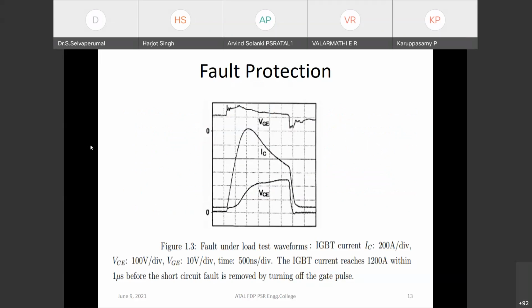So the slide shows fault under load test waveforms. IGBT current is denoted as IC, 200 ampere per division, and collector emitter voltage 100 volt per division. Gate emitter voltage is 10 volt per division. Time is 500 nanosecond per division. Right. So the IGBT current reaches 1200 ampere within 1 microsecond before the short circuit fault is removed by turning off the gate pulse. So here the dynamic performance of current sensors plays a crucial role in the fault protection system of motors and power converters.